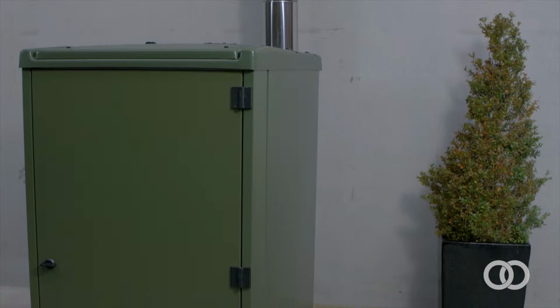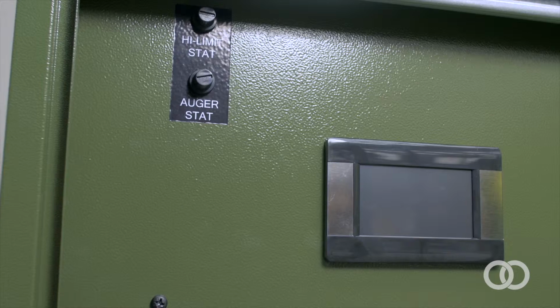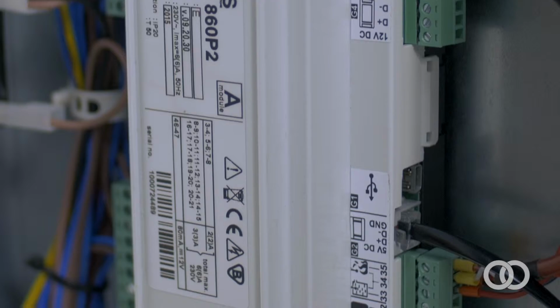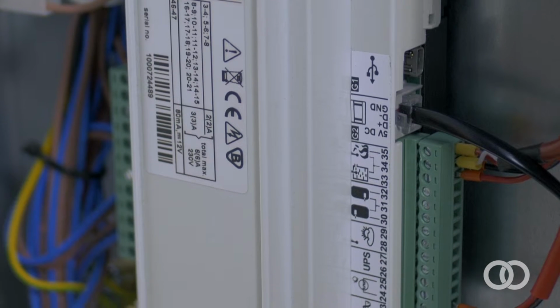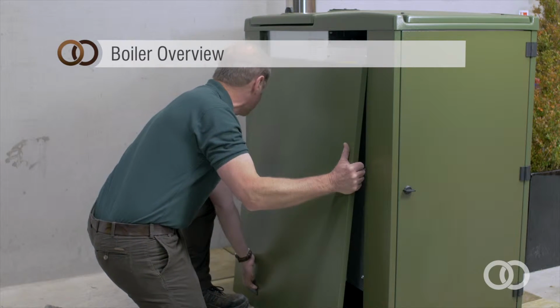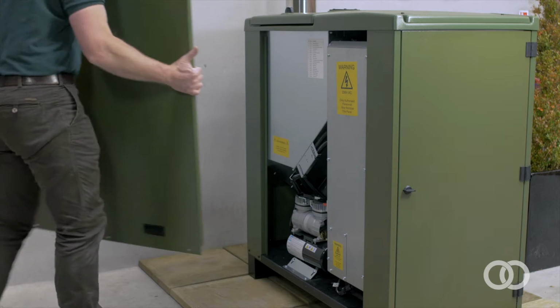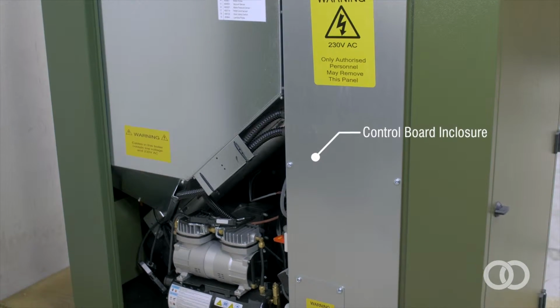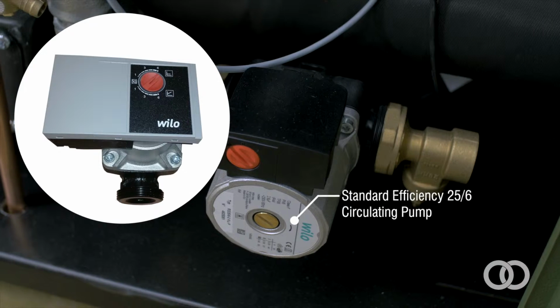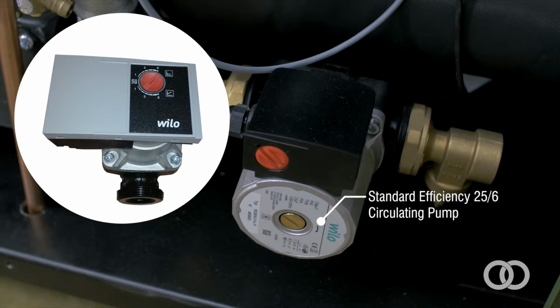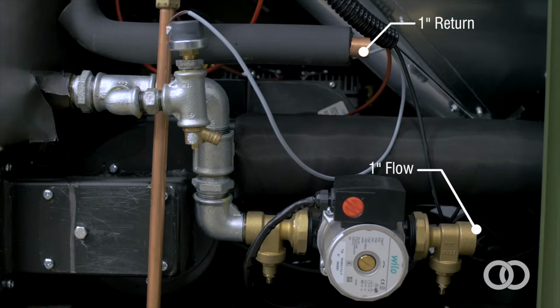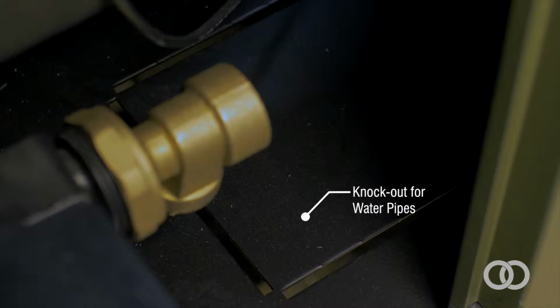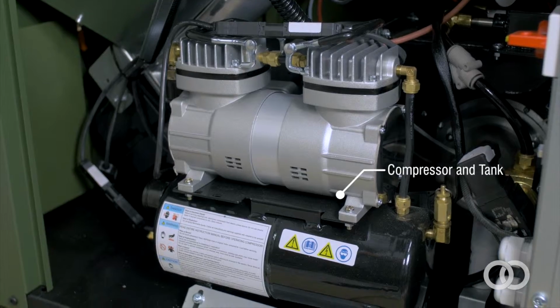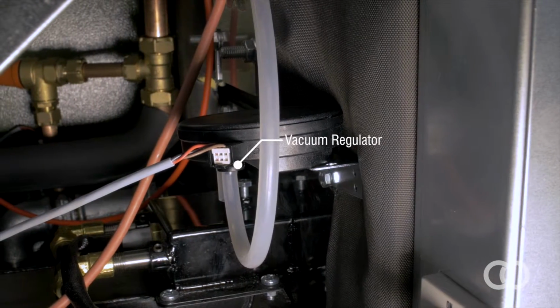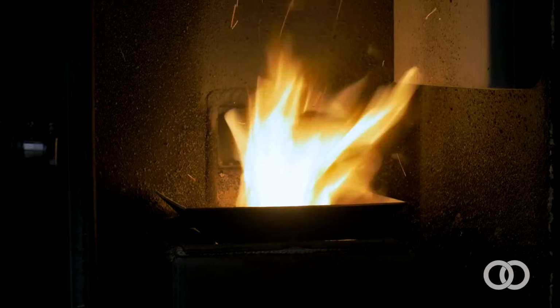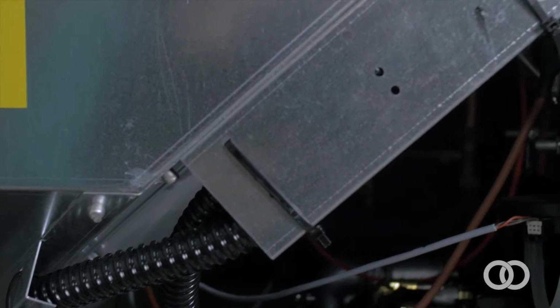This video describes the installation of the external 15 kW, but the same principles apply to all internal and external models, and the controller and key components are exactly the same on all domestic models. Unique new features on the external iGen are easily removable side panels, easily accessible control board enclosure, a new ERP energy efficient Wilo variable speed pump as standard from August 2015, flow and return connection pipes that can exit through a knockout in the base, unique compressed air cleaning system, a vacuum regulator which ensures negative pressure is maintained in the combustion chamber. All wiring is heat resistant and sleeved.